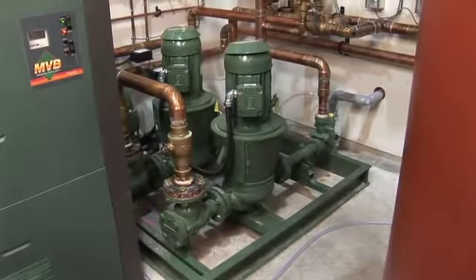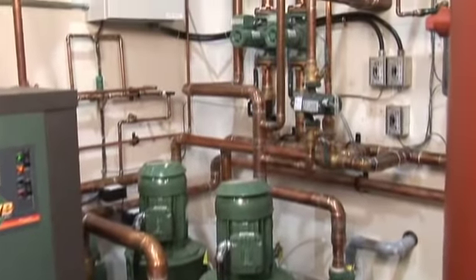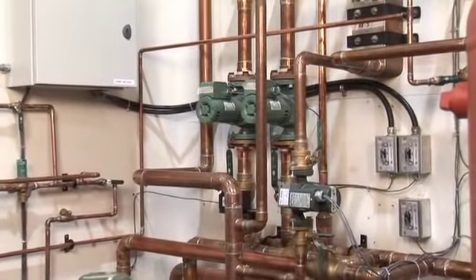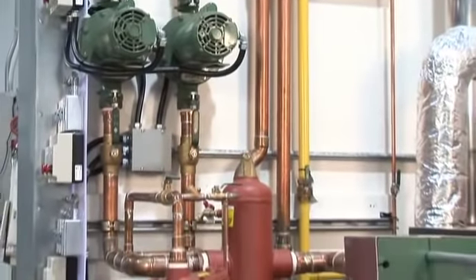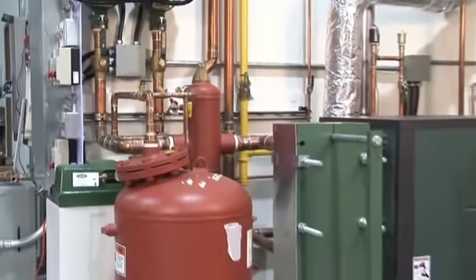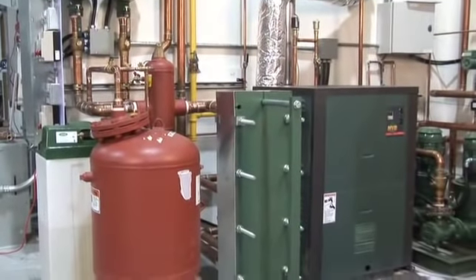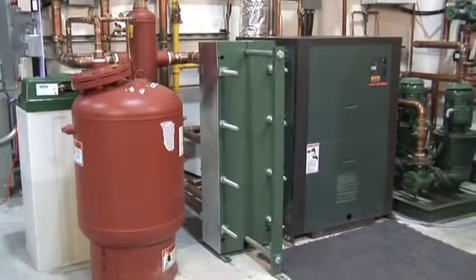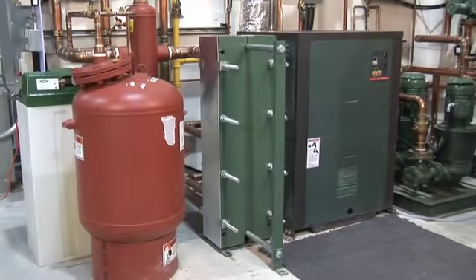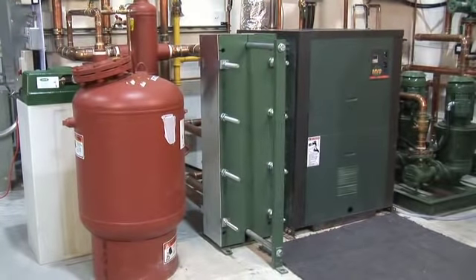Our system here consists of a heating loop and a cooling loop. We have generation equipment here to this one side, a chiller on the roof, and the chiller is fed into a heat exchanger, and that heat exchanger provides the cool water, 42-degree water for the cooling loop. Next to the heat exchanger is our boiler, and the boiler produces our hot water for the heating loop at 180 degrees. The advantage of our LoFlo system is that we can use much smaller piping at a higher delta T to deliver the cooling fluid to the terminal unit.